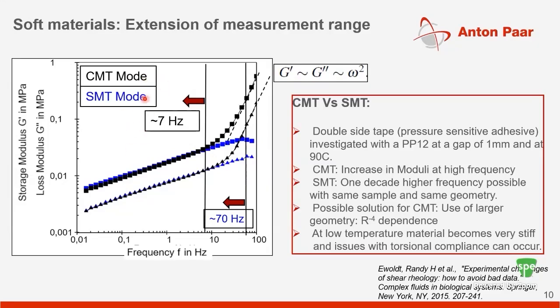Now, the advantage of having a multi-drive is you can actually investigate the same sample in SMT mode. And when you have a separate motor transducer type device, you can actually see that you don't really see this spurious increase which happens in the CMT mode. And you can extend the characterization by almost a decade in frequency. So this slide hopefully shows you advantages of having a dual motor type setup where you can do both CMT and SMT type experiments on this PSA, where at least I showed you through this frequency sweep experiments.